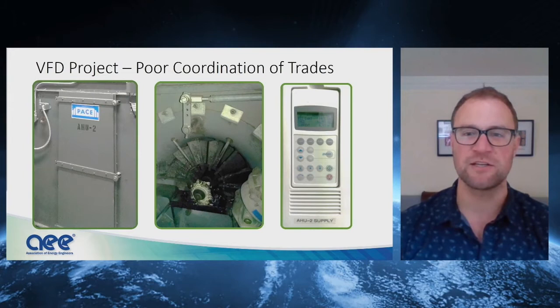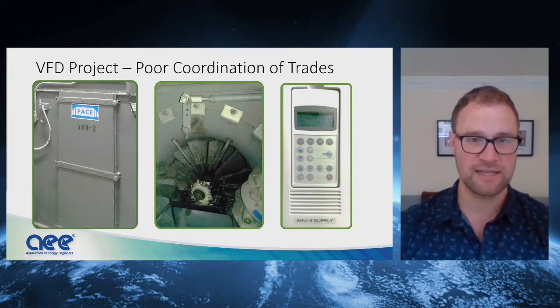So we were out there doing an energy study, walking through the building, and at first glance, your instinct as an energy engineer is to think, oh, I see this unit already has a VFD, move on to the next thing, right? No opportunity here. Well, we opened up the door to take a look inside, and sure enough, as you can see in that middle picture, these are inlet guide vanes, right? An inefficient way of control.